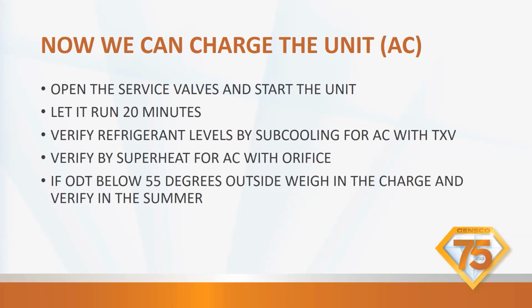Start the unit and add charge to subcooling in air conditioning mode. Okay. So we're going to let it run for 20 minutes. We're going to add our refrigerant a little bit at a time until we reach the subcooling that's listed on the outdoor unit.